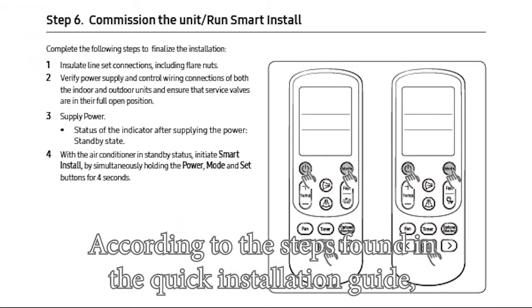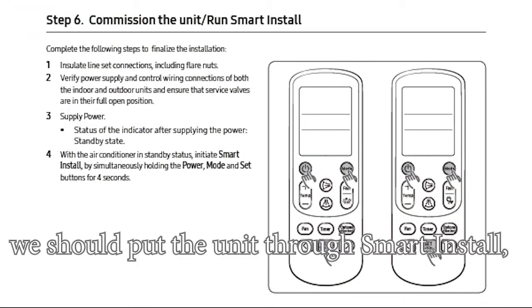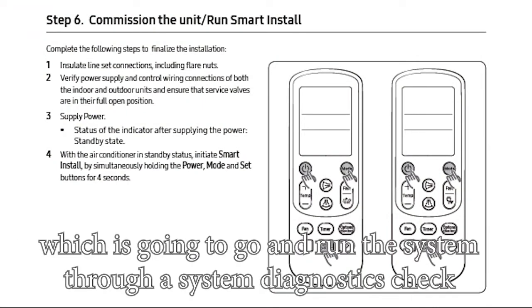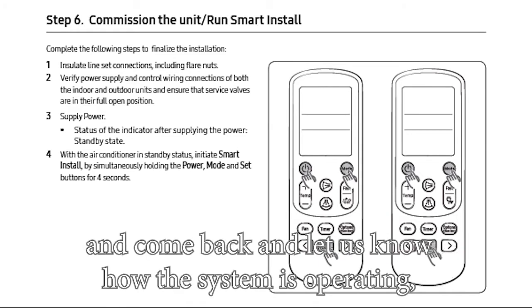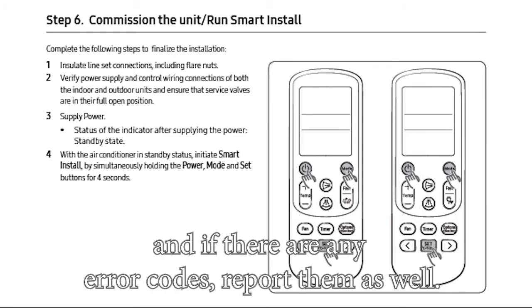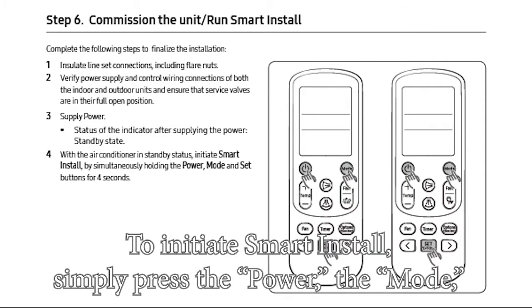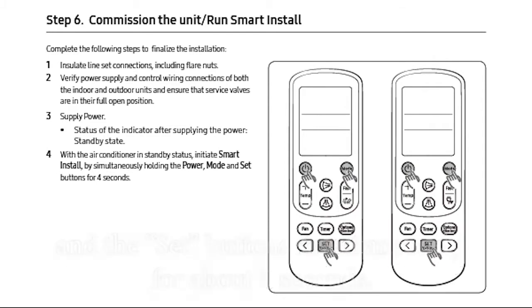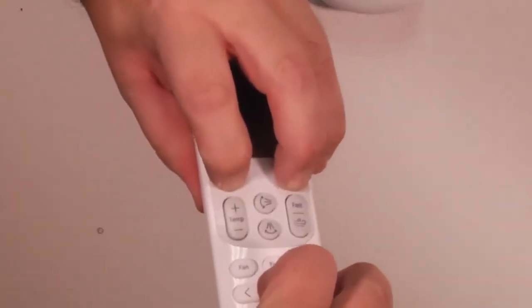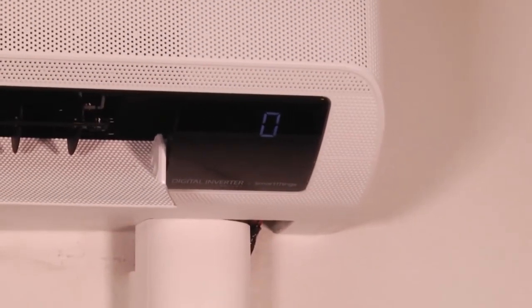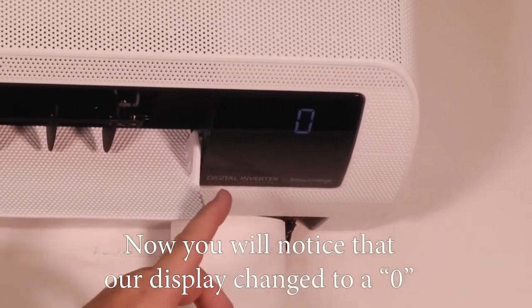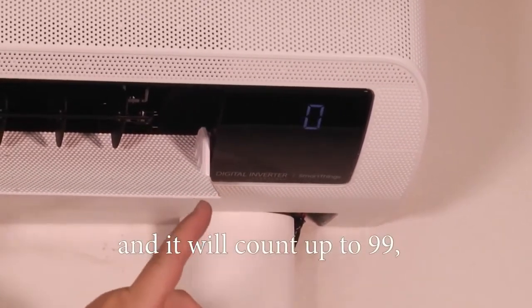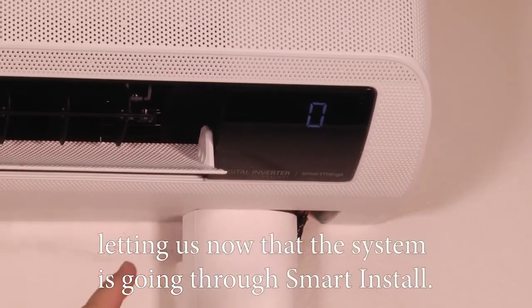Now, according to the steps found in the quick installation guide, we should put the unit through Smart Install, which is going to go and run the system through a system diagnostics check and come back and let us know how the system is operating, and if there's any error codes, report them as well. To initiate Smart Install, simply press the power, the mode, and the set button simultaneously for about 5 seconds. And now you'll notice that our display changed to a 0, and it'll count up to 99, letting us know that the system is going through Smart Install.